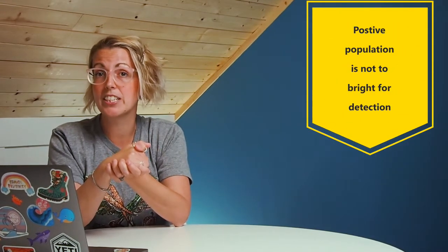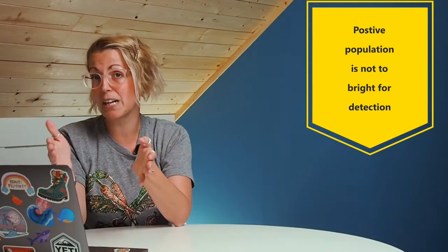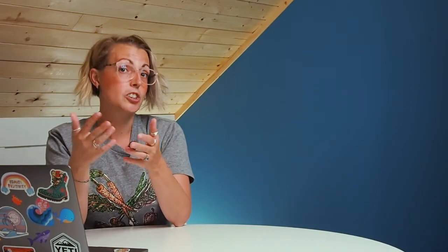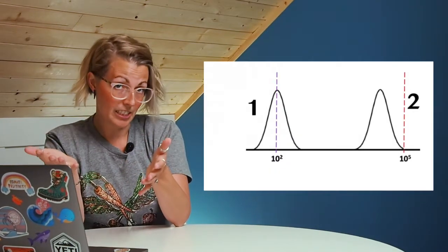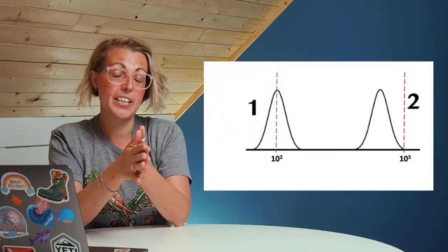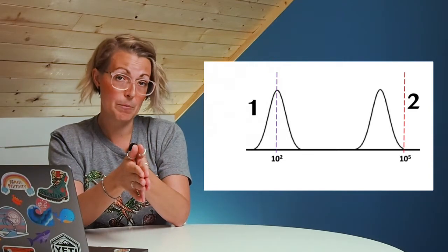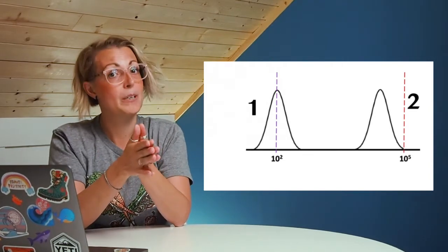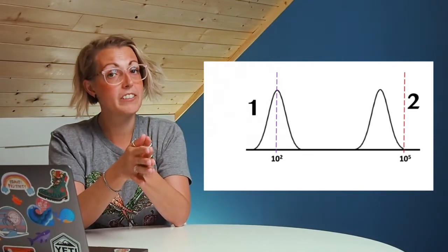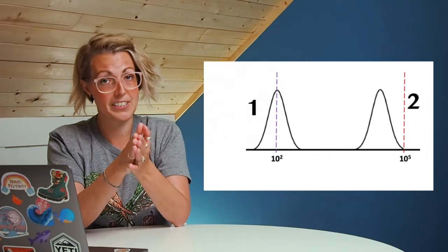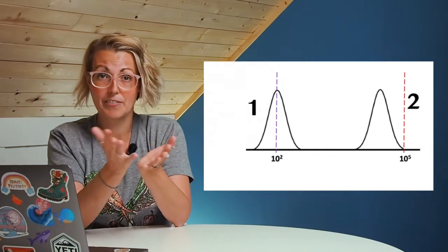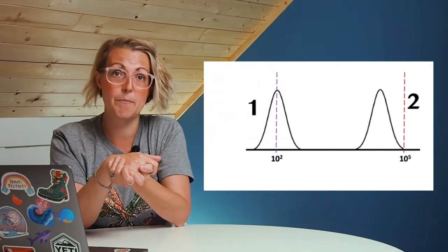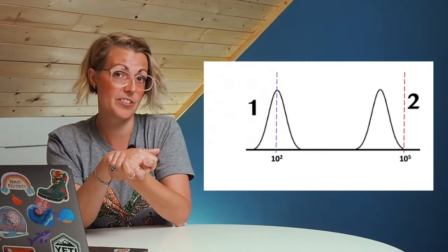The second thing you want to make sure is that your positive population isn't too bright for the instrument to detect, so it's on the linear scale of the detector. When you get too bright, you no longer get accurate representation of your fluorescence intensity. Generally, if you set your negative sample centered around 10 to the 2 and make sure your positive is no brighter than 10 to the 5, you're going to be okay on most standard digital instruments.